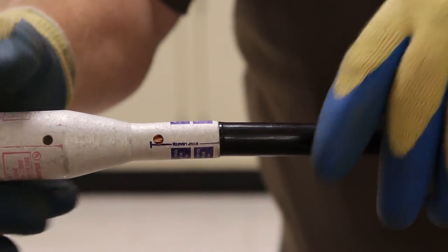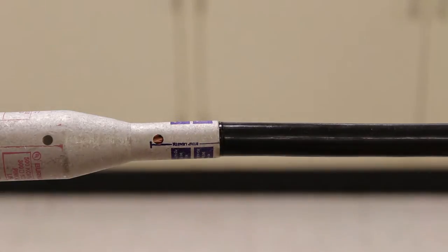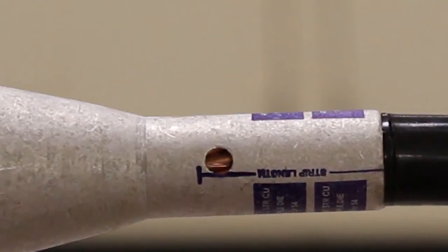Once you have stripped the wire, insert the cable into the connector. Insert the connector in the die and ensure the cable is fully inserted. The cable strands must be visible through the inspection holes.